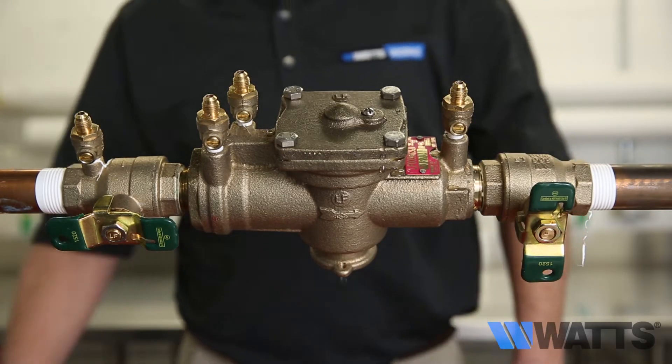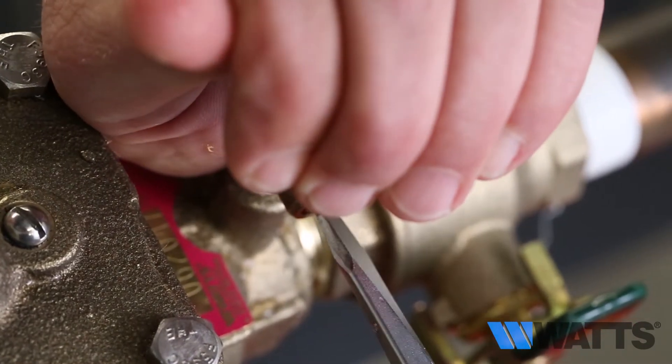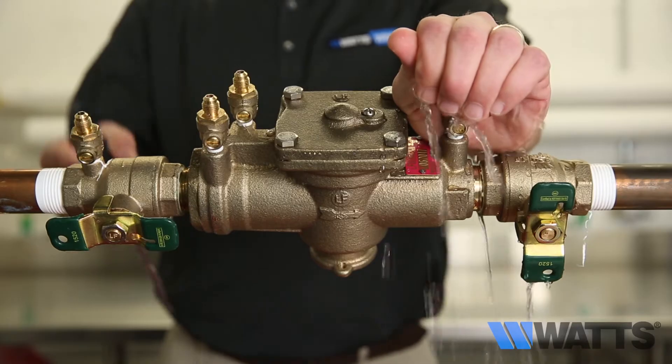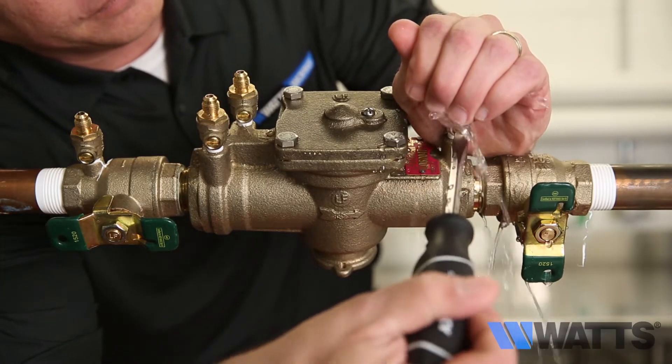If it does not stop, open test cock number four to create a downstream flow. If the discharge of water from the relief valve vent becomes less or stops, it most likely indicates you have a fouled second check.